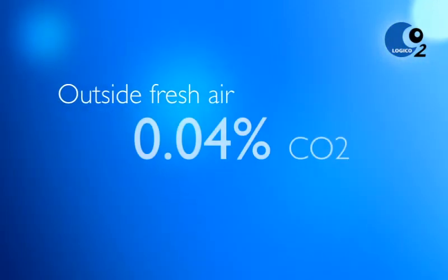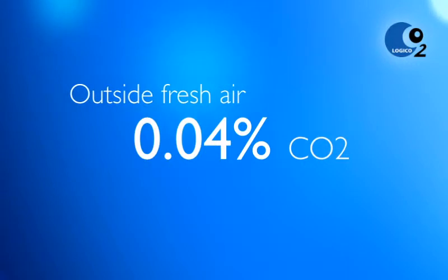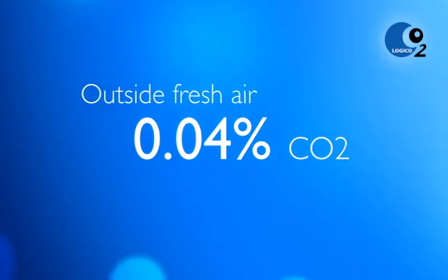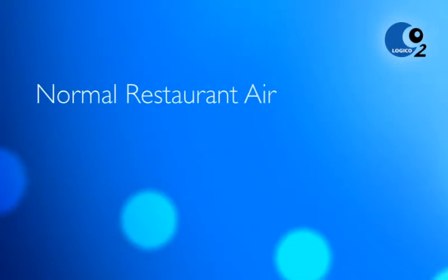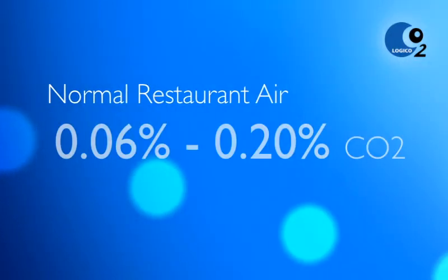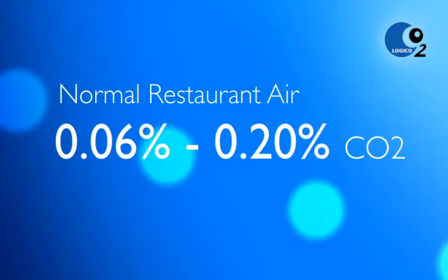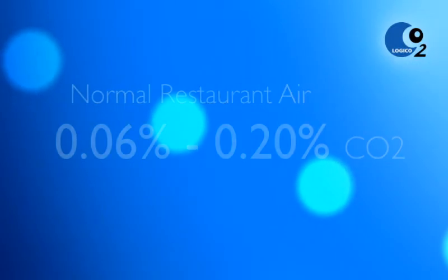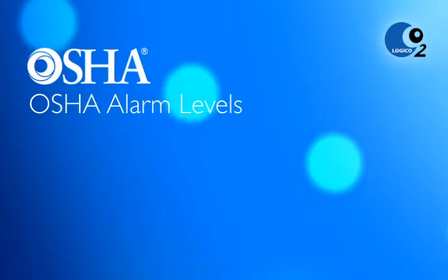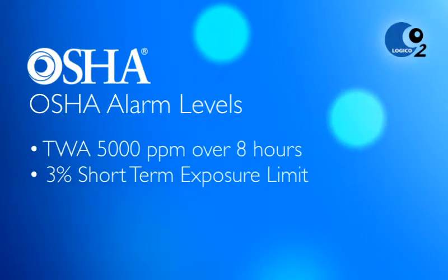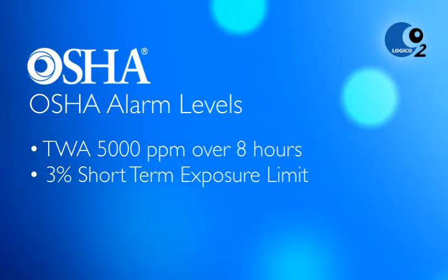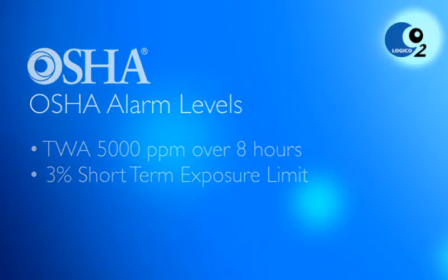The outside fresh air has about 0.04% CO2. Under normal conditions, the CO2 concentration in the store will be between 0.06% and 0.20%. The alarm levels set by OSHA are for long-term exposure, called time-weighted average, 5,000 ppm over 8 hours. Short-term exposure, 10 minutes, is 3%.